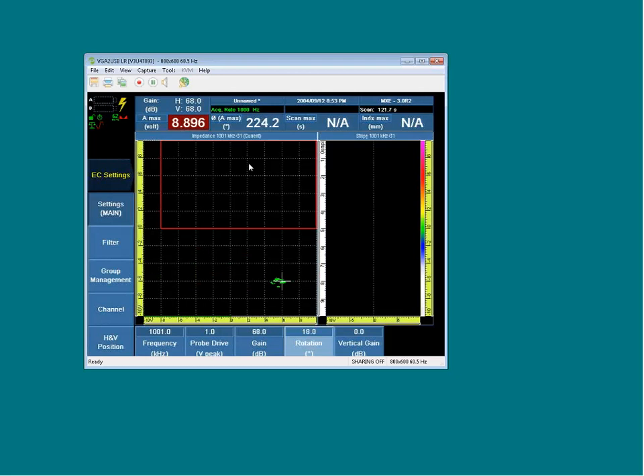We obviously want to use the C-scan view. But right now, I'm still in the eddy current principles, so still in step 1 of calibrating, making sure my signals fill that screen. All right, that's much better. So I start to have eddy current looking like signals, but 32 of them, because my probe has 32 channels.